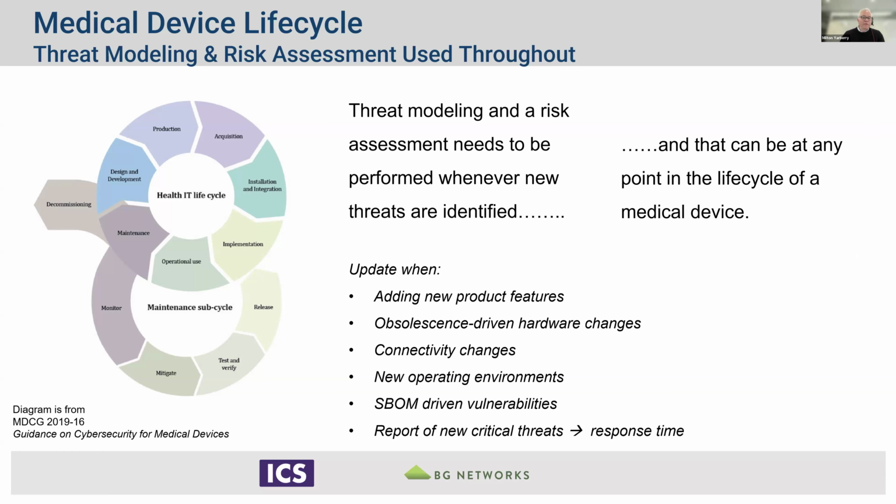Also new operating environments. If a device was only used clinically in the hospital first, but then became a home device, for example, that new operating environment would require an update. And of course, SBOM-driven vulnerabilities. As new vulnerabilities are discovered in the market and you're doing your due diligence on your device in the field, as those vulnerabilities come to light, you may have things you need to fix, and then of course you'd want to update the modeling, et cetera.